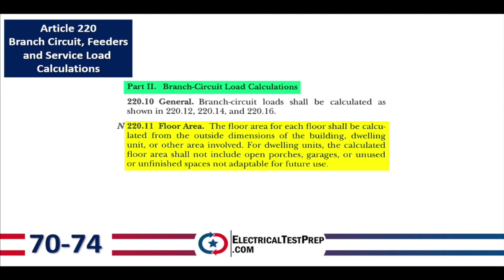In this article, we're going to learn how to do our dwelling unit calculations. One of the first pieces of information we need is the square footage of the area — basically just heated area. Open porches, garages, or unused or unfinished spaces not adaptable for future use are excluded. For example, a basement with inadequate ceiling height would not be included.